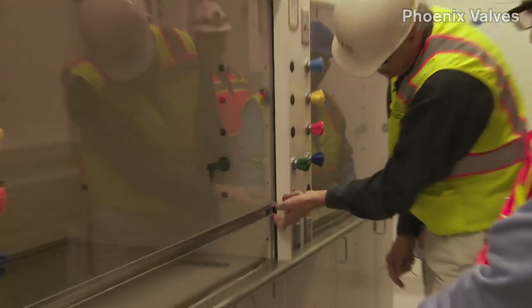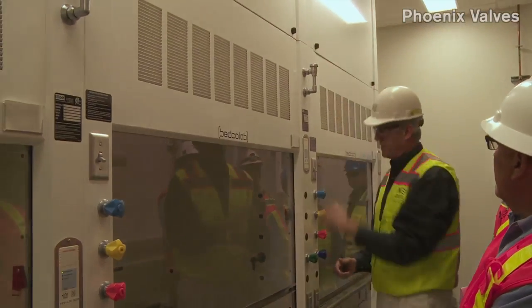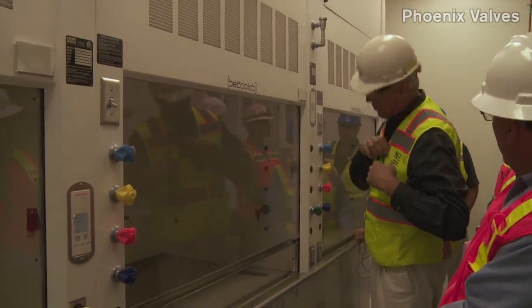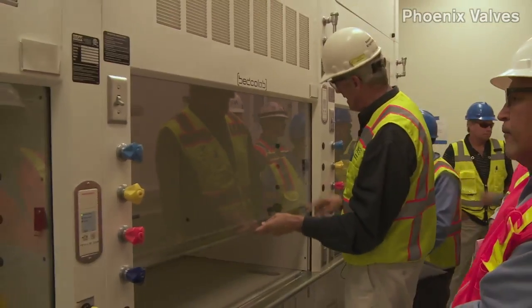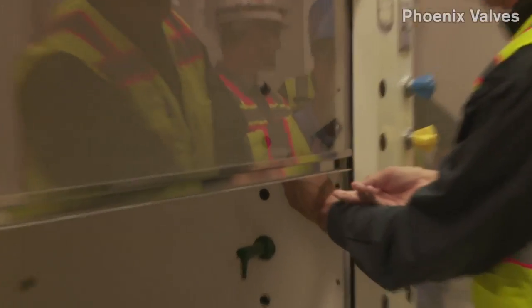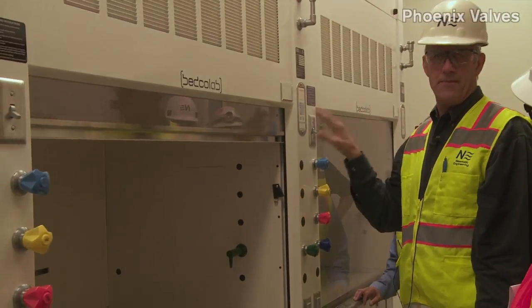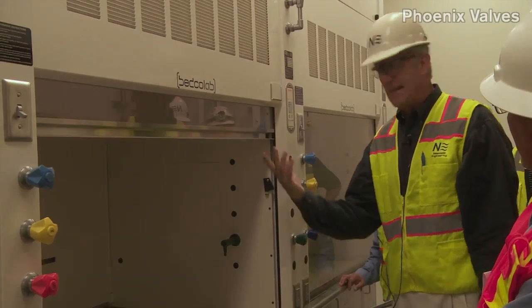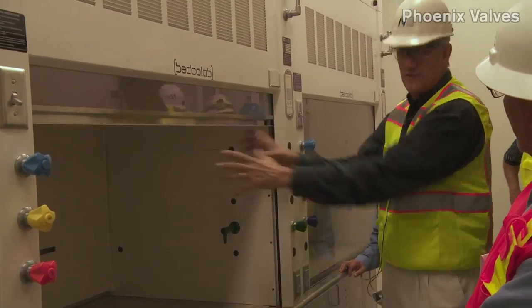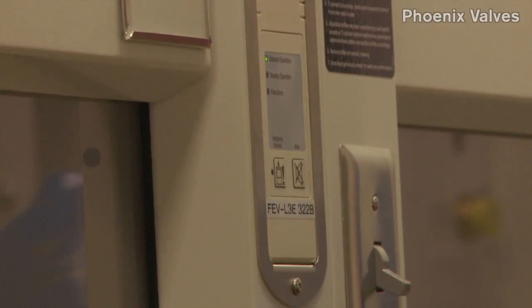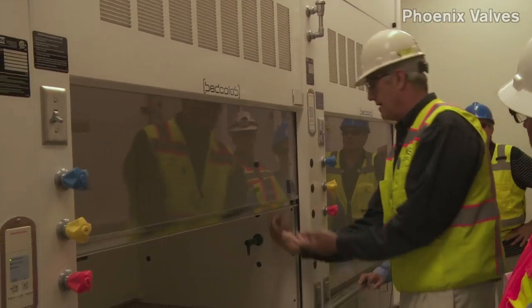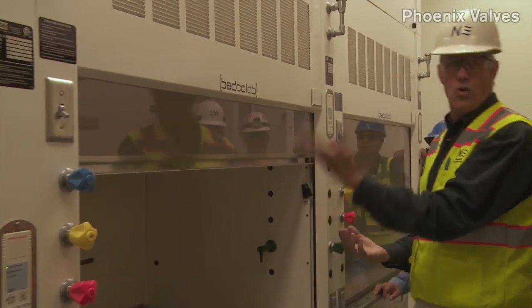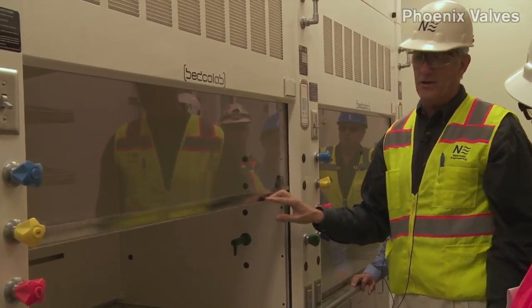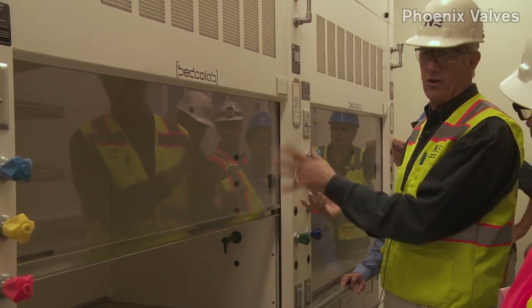That's attached to the grab hold at the bottom of this sash, and it's mounted up here. That's measuring the sash height. There's only enough airflow designed in to get you to this sash stop. So if someone reaches in and defeats the sash stop and takes this higher, the hood will go into alarm. Notice that's the flow alarm. So someone says, hey, my hood's alarming. You raised your sash too high. You're only supposed to, this is for setup. You can mute that audibly, but the red light will stay on. During setup, you can work with it up here. But when you're ready to do your science, bring it back down, get back into the green zone. So if someone calls with an alarm, one possibility is they've raised their sash above the sash stop. All they got to do is lower it back to the zone where it was designed to be operated, and it'll go out of alarm.